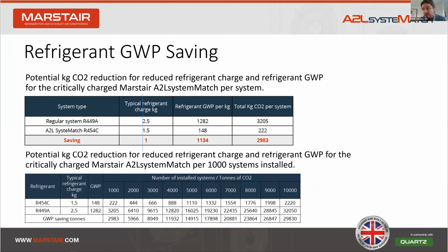Clearly, the bigger benefits are with the refrigerant GWP saving. So if we compare a typical R449A 3 kilowatt system on approximately a 10-meter pipe run to the new R454C system match, combining the reduced refrigerant charge with the reduction in refrigerant GWP, this gives a 93% reduction, which equates to 3 tons of CO2 per system. Extrapolating that over 10,000 systems, that saves 30,000 tons of CO2, which obviously makes a massive difference in helping the industry meet its obligations.